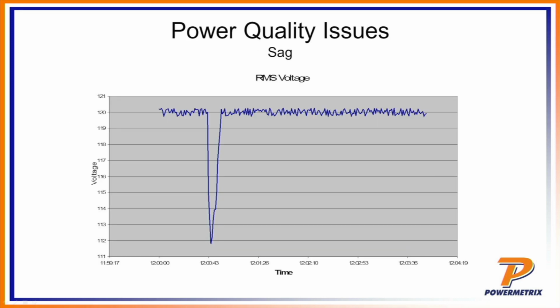If we look at a graphical representation of this, what we've got here is a sag. If you look at our time base, this is just over the course of a few seconds. The dip is going nominally from 120 volts all the way down to 112 volts. So you had about an 8 volt dip there. And on the time base, that lasted much less than 1 second, probably a few tens of milliseconds.